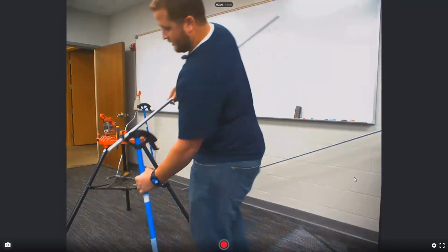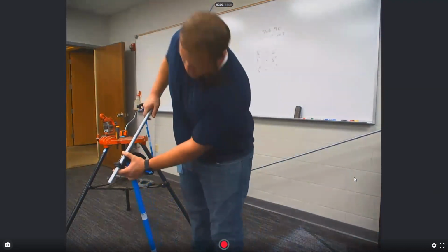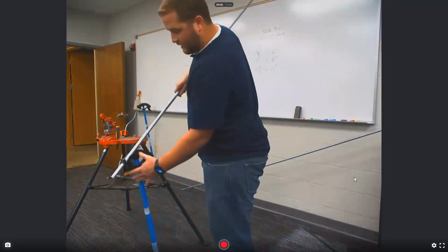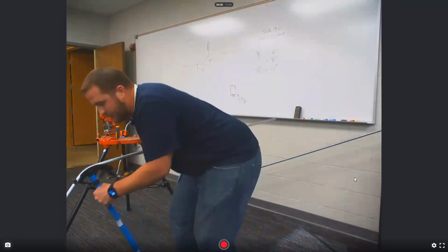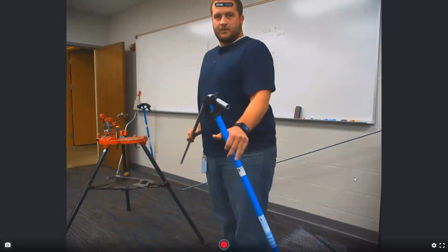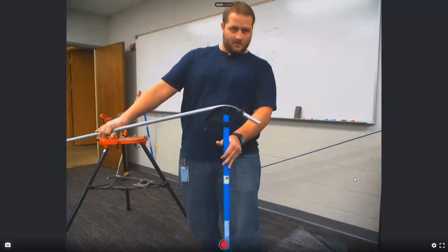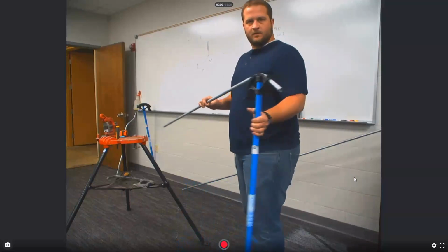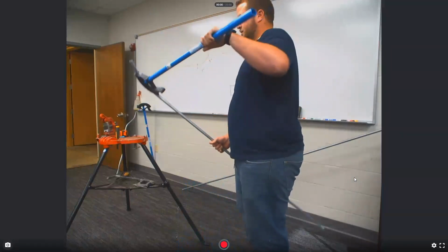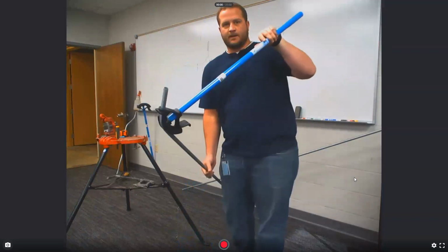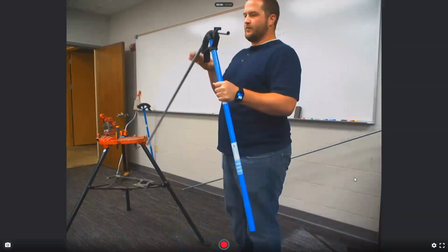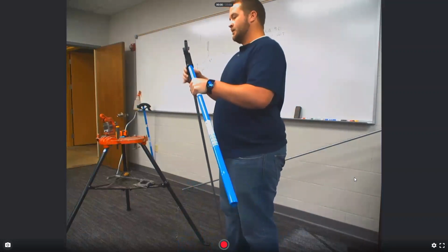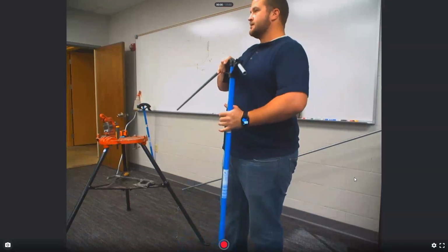Be careful where the end of your pipe is. Push down and get the bend started. So you see what it looks like so far. And then I put it on the ground. The reason I do it this way is because if I put it on my mark without having made that bend and then go to set it on the ground, it tends to move. When you bend it a little bit first, it tends to stay in place a little bit better.